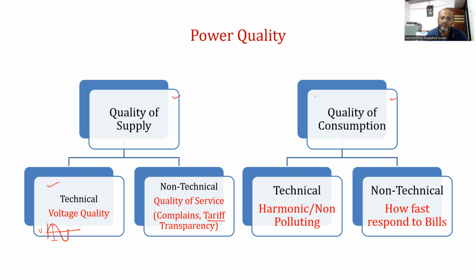Similarly, the quality of consumption is very important, because the current is related to the type of consumer. Again, there are two parts: one is technical and the second is non-technical. In the technical part, either the consumer is producing harmonics or is non-polluting. Definitely, it depends on which type of load is there. Either it is causing unbalance, or the power factor is very poor, which means it will draw more reactive current.